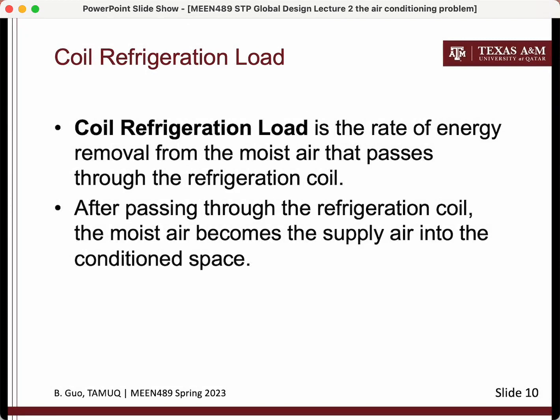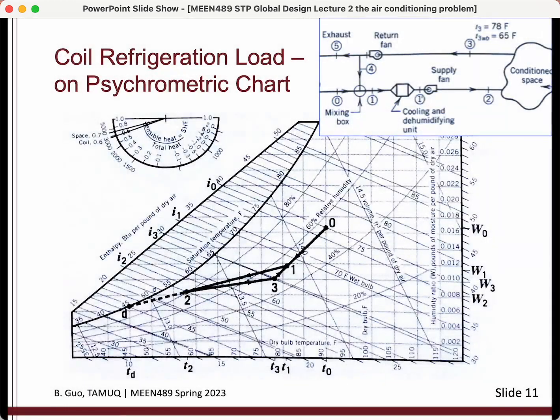The return air leaves the conditioned space and enters the cooling equipment, which contains a coil through which a cold fluid flows, and heat transfer removes heat from the air. The cooling equipment cools the return air plus some fresh air to produce the supply air. The coil refrigeration load is usually greater than the cooling load because of the need to cool fresh air from the ambient environment. The coil refrigeration load concept is shown on a psychrometric chart, where point zero is the condition of fresh air from the ambient and point three is the condition of return air from the conditioned space.